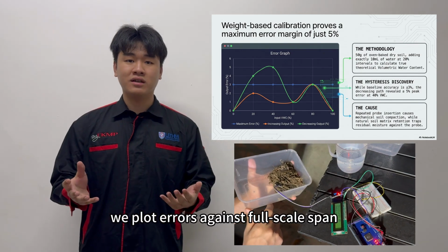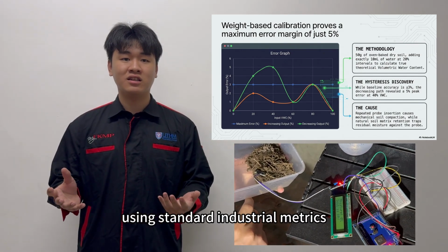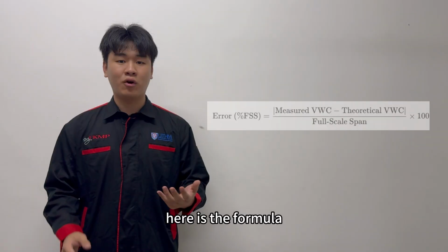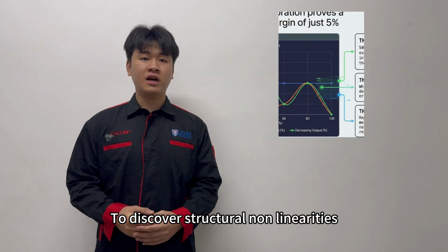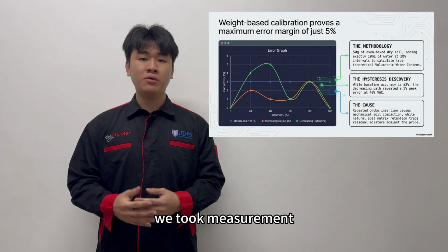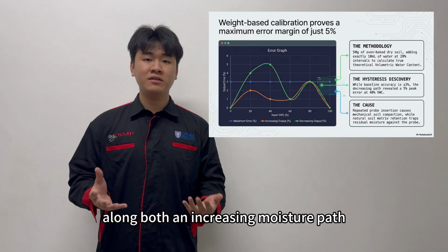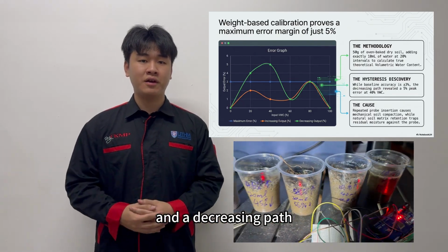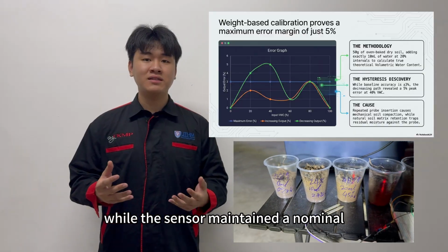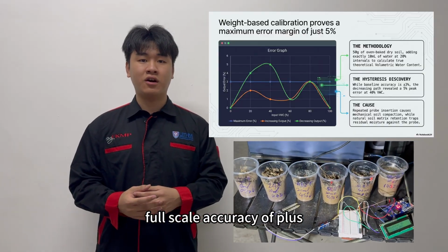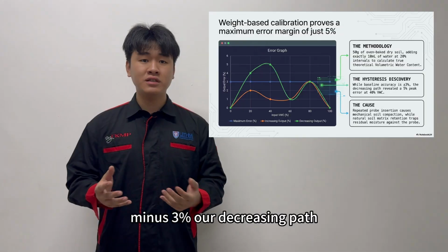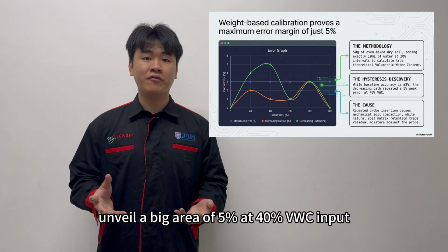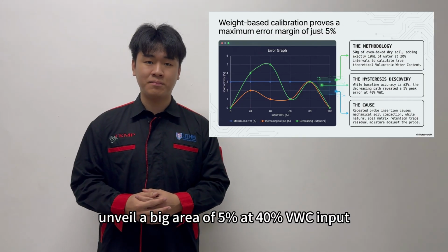We plot errors against full scale span using standard industrial metrics. Here is the formula. To discover structural non-linearities, we took measurements along both an increasing moisture path and a decreasing path. Our data confirmed that while the sensor maintained a nominal full-scale accuracy of ±3%, the decreasing path unveiled a peak error of 5% at 40% VWC input.